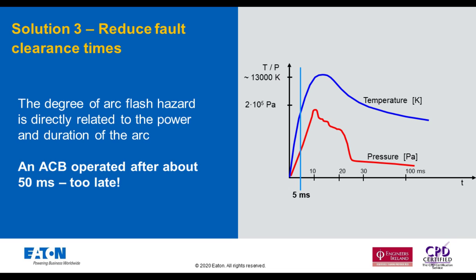What you've got to note is that when you're including arc mitigation systems in assemblies, the new BS EN 61439 Part 2 and IEC standard now advocates 61641, and a new standard called IEC TS 63107, which covers the integration of internal arc mitigation systems in PSC assemblies. It tests the application of these new devices within an assembly to make sure that it activates correctly under arcing conditions, and things like nuisance tripping and switching on directly onto an arc fault are all covered. It's okay just implementing a 947 device into an assembly and thinking it's going to work, but this new technical specification is one way of demonstrating that it does work.